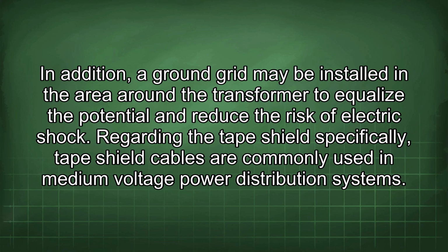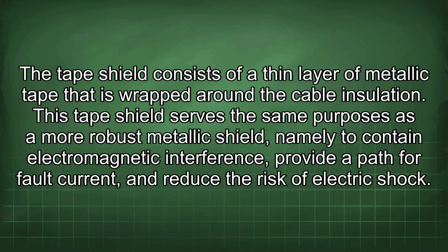Regarding the tape shield specifically, tape shield cables are commonly used in medium voltage power distribution systems. The tape shield consists of a thin layer of metallic tape that is wrapped around the cable insulation. This tape shield serves the same purposes as a more robust metallic shield, namely to contain electromagnetic interference, provide a path for fault current, and reduce the risk of electric shock.